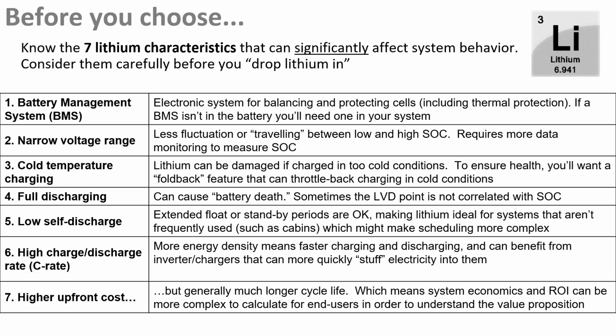Some lithium manufacturers I know have said, oh, you can discharge it all the way to 0% state of charge. Well, it's not really. You have to still leave some of that electrolyte in there in order to be able to recover it. Otherwise, you're risking permanent damage. So that's one additional thing. A lot of people say, okay, well, with lead acid, I was used to not being able to discharge below 50% state of charge. With lithium, you really want it to be at around that 20% state of charge threshold in order to promote and maximize your cycle life and avoid risking damage to the battery.